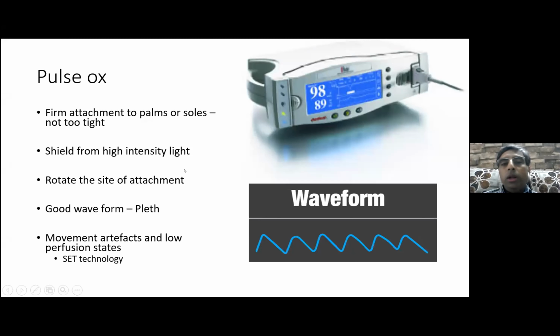Another important thing is phototherapy. We all use it many times in sick babies and any other baby with jaundice. This high intensity phototherapy light can interfere with the readings on the pulse oximeter, because this is also light and it also works on the principle of light. So if the light impinges on the probe, that will give you erratic signals. So you have to shield the pulse oximeter probe from the light, so that it will not affect the readings.